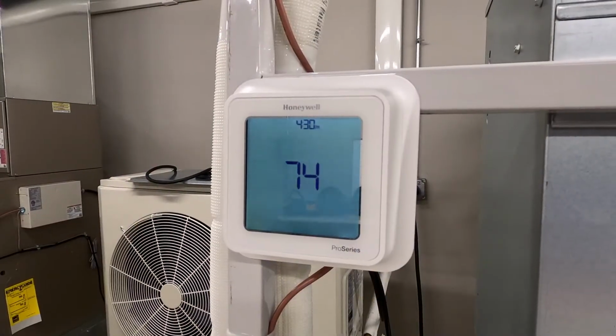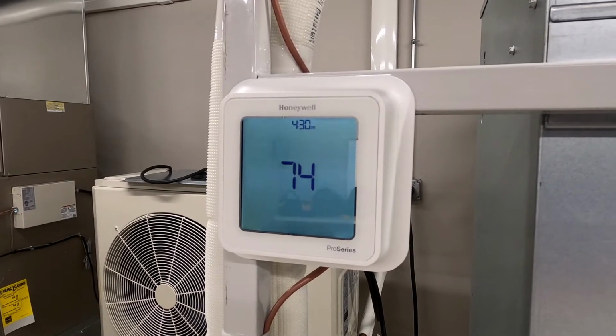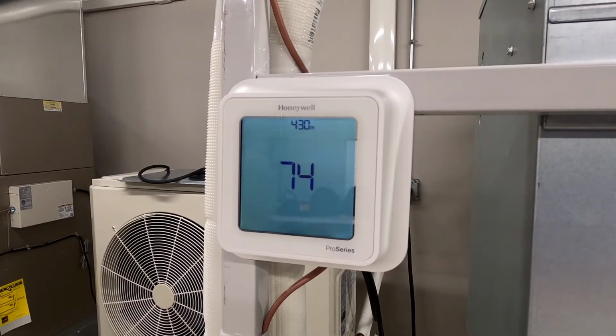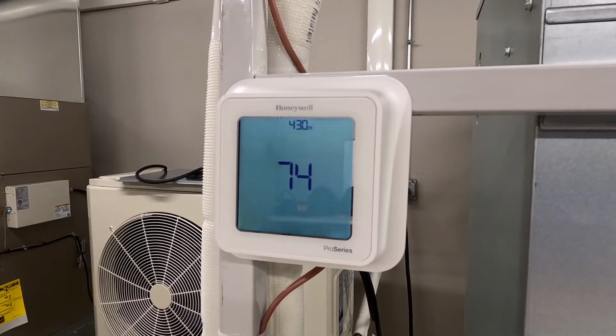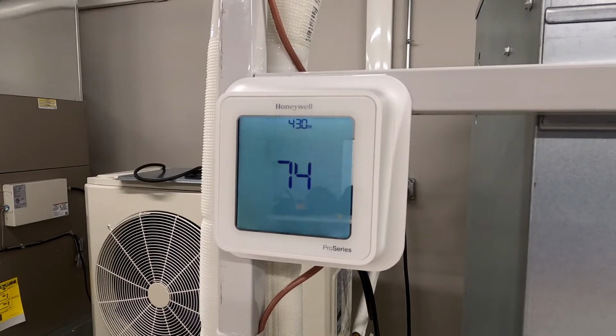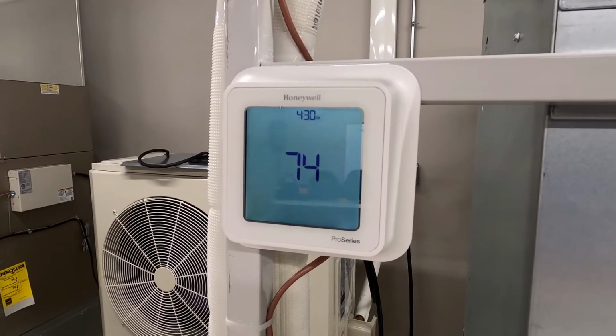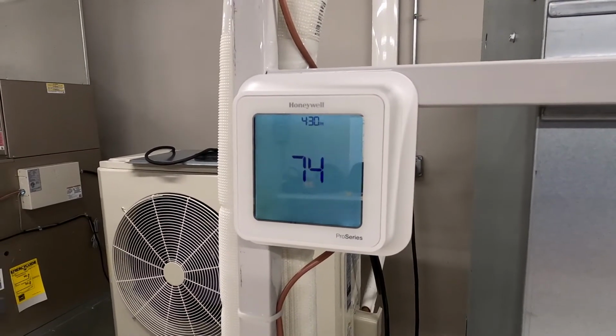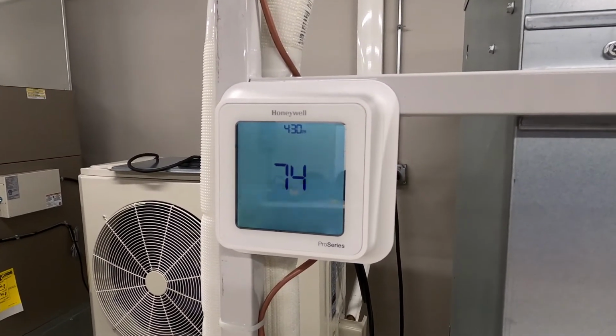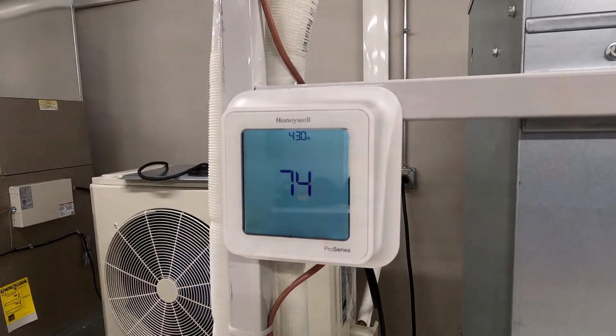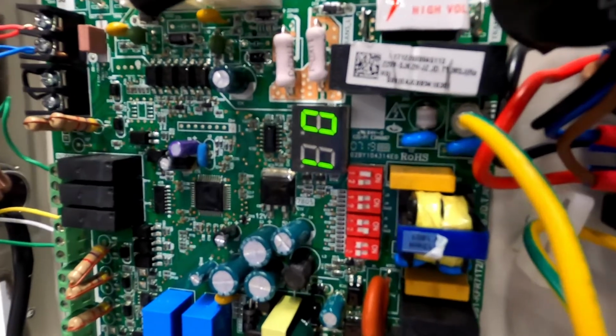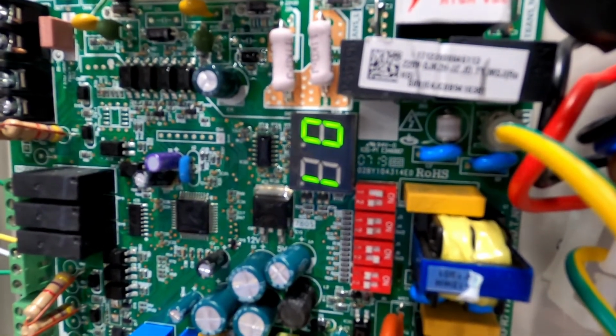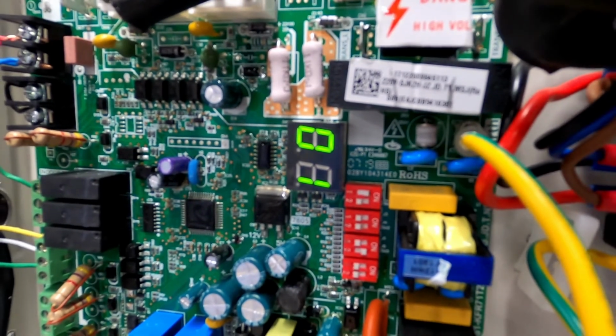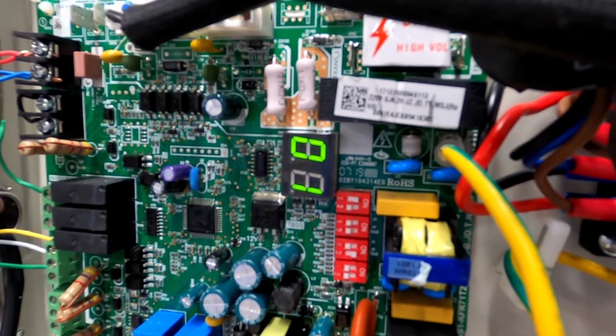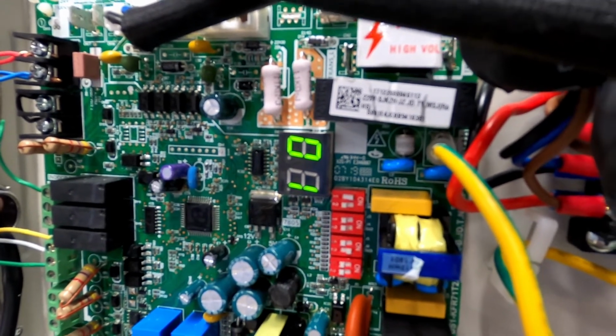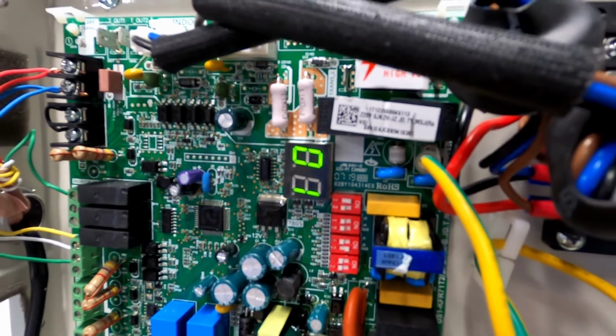A couple notes when installing the thermostat and configuring it with this setup: many different types of thermostats can be used, and generally that depends on the individual job. You want to make sure that you set it as a conventional system with 1 stage of cooling and 2 stages of heat. Some thermostats give you the ability to control when second stage heat comes on, so you can also set that according to the needs of the space. When you're starting the system up, to verify that your 24-volt interface is calling for the correct mode based on what the thermostat is calling for, when you're calling for cooling, you'll see a 0-1. When there's a call for heat, you'll see a 0-2. And then when there's a call for fan only, you'll see a 0-3.